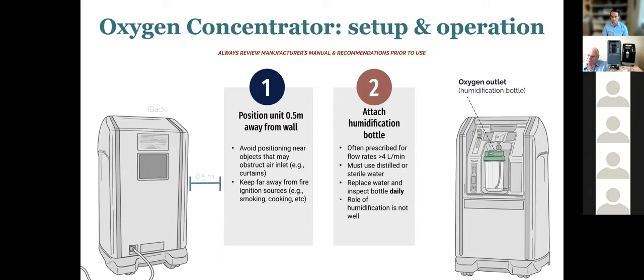If you do use humidification, you need to use clean water. Water that's not kept clean can cause buildup of bacteria and potentially increase the risk for infection. Ideally, use sterile or distilled water that doesn't have particulate matter or minerals in it that can over time potentially lead to buildup and occlusion of the device.